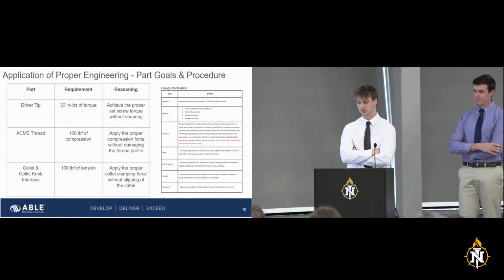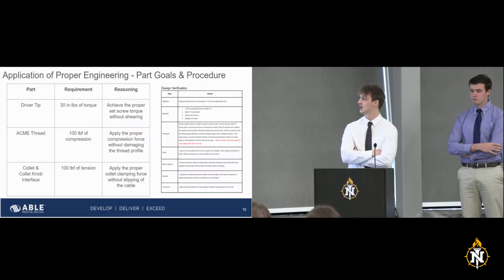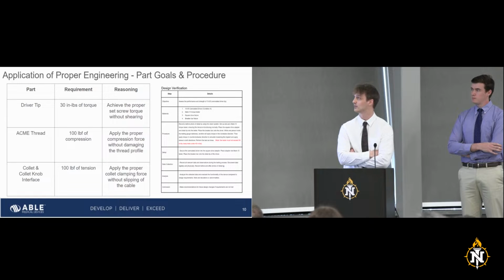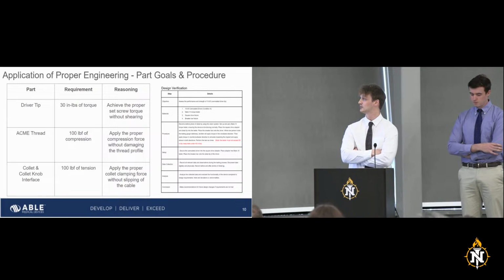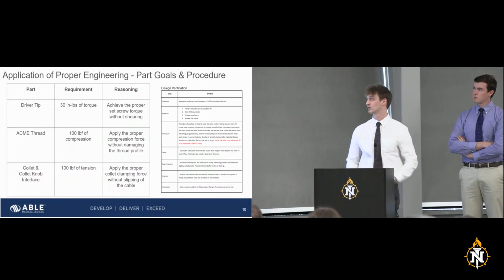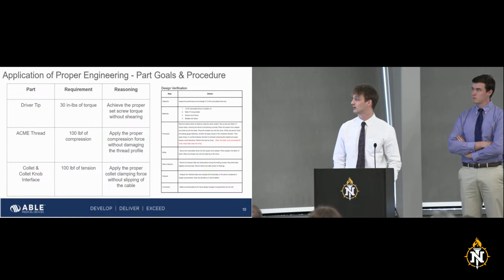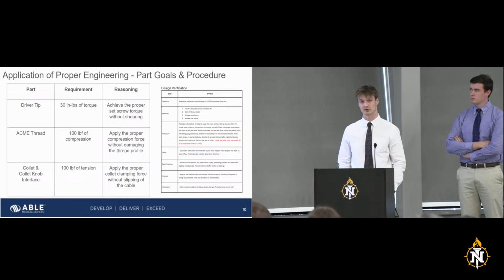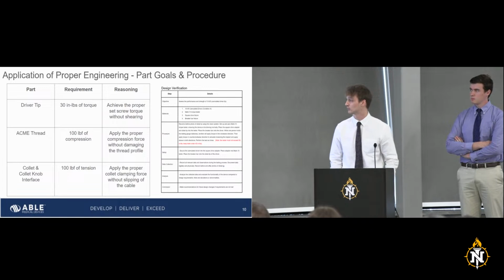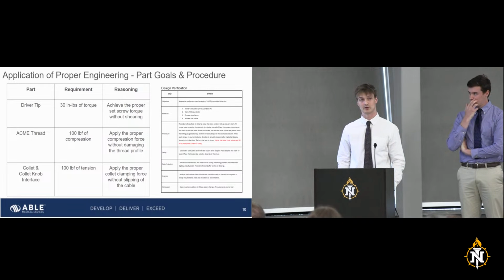Then into the part goals and procedure. So we had 3 parts that we were mostly worried about: the driver tip, the Acme thread, and the collet and collet knob interface. For the driver tip, we wanted to apply 30 inch-pounds of torque. This was to achieve the proper set screw torque without shearing the cannulated driver tip. Then the Acme thread, this needed to withstand 100 pounds of force of compression. This was to apply the proper compression force without damaging the thread. And then the collet and collet knob interface, this was the needed requirement of 100 pounds of force in tension to apply the proper clamping force to the collet without the cable slipping.